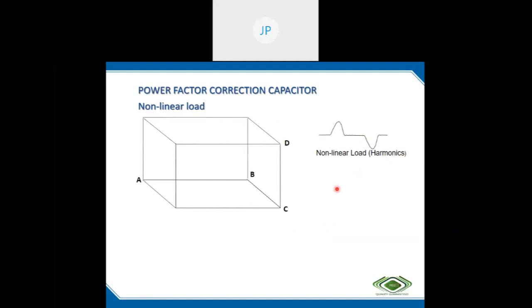So let us see the power diagram of the nonlinear load. The wave shape of nonlinear loads is distorted, so it will have harmonic components. The power diagram again consists of power in kilowatts, kVAR, and a third new component, distortion reactive power. Instead of the kVA as AC, now it will be AD, and this is referred to as true apparent power. It has the influence of two factors: one is the displacement reactive power, another is the harmonic distortion due to THD.